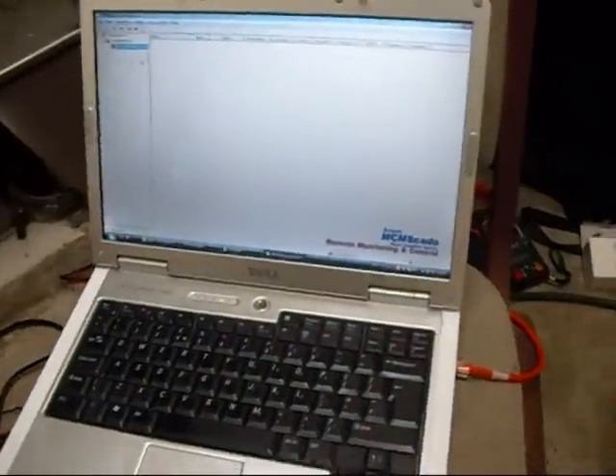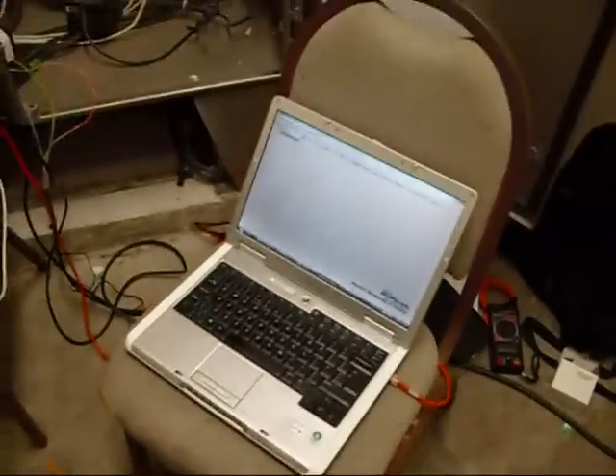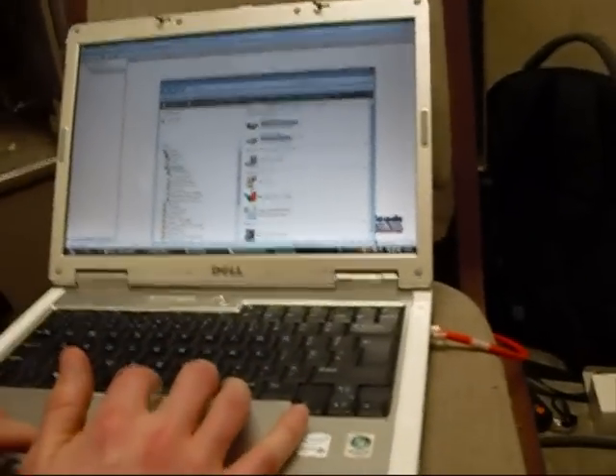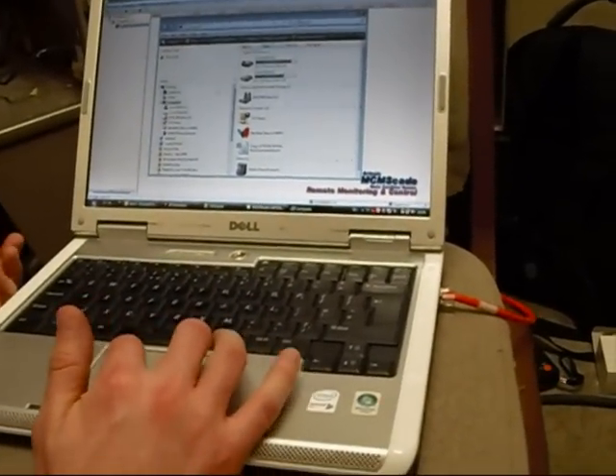We've now connected the Moxa unit. As you can see, we've got the null modem adapter connected to the side of the box. We then have a serial cable that goes all the way around to the Moxa unit. The Moxa unit is then connected by a crossover Ethernet cable to the computer. What we're going to do now is change the TCP settings so that we can communicate with the Moxa. Our computer is connecting via a crossover cable, so it needs to think it's connected to the same network.